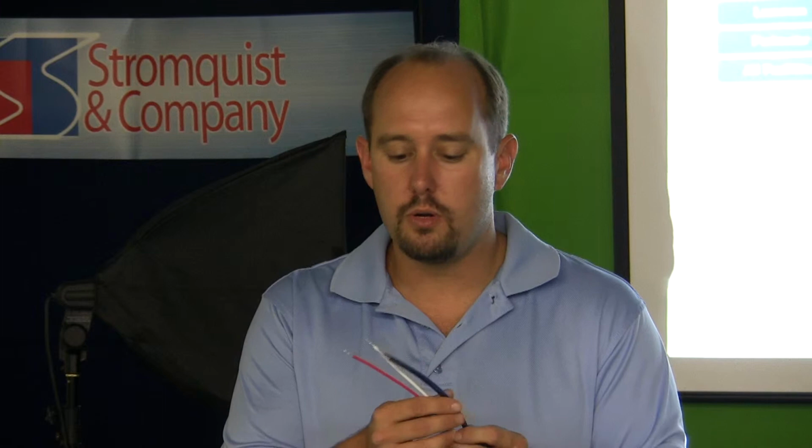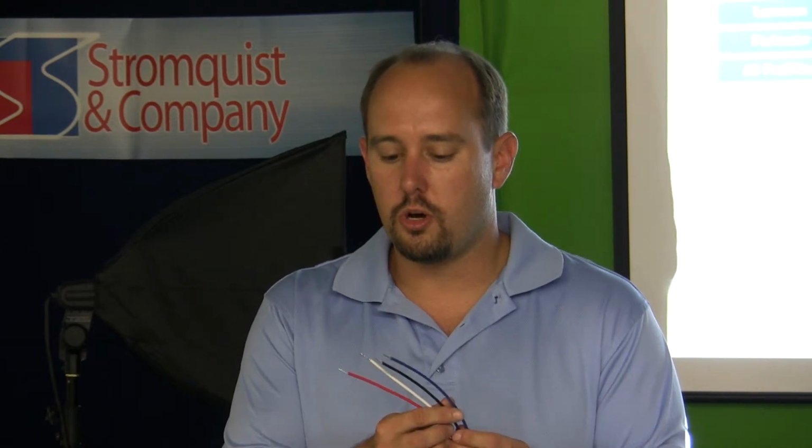By NEC code, you can do what's called a double tap onto a breaker. So you can use an existing breaker and land our cables on top of that as well to power it. It's always preferable to use a separate breaker if you can, but sometimes you've got a panel that's full and you're trying to be in there. So do what you have to do.